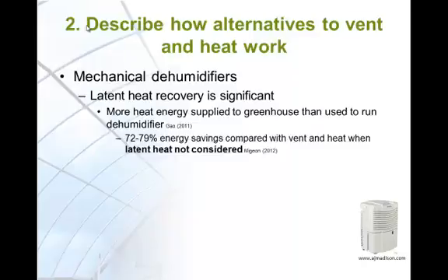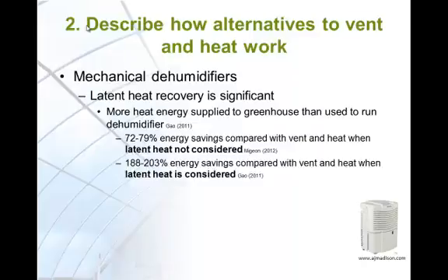When latent heat is not considered, Migeon reported 72 to 79% savings in comparison between use of a mechanical dehumidifier and a conventional vent and heat operation. When latent heat is considered, Gao reported 188 to 203% savings in comparison between the use of a mechanical dehumidifier and a conventional vent and heat operation.